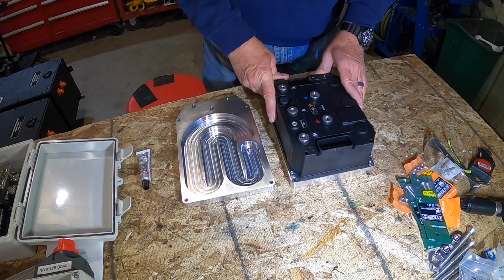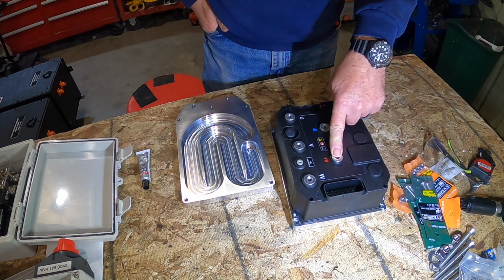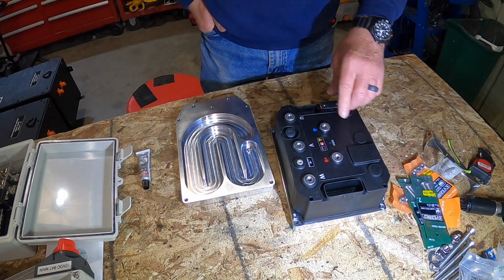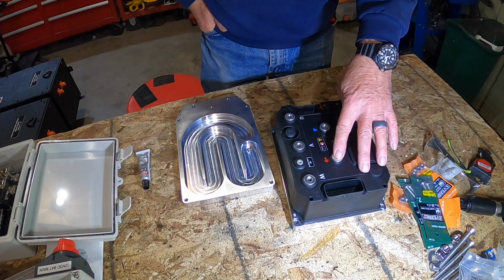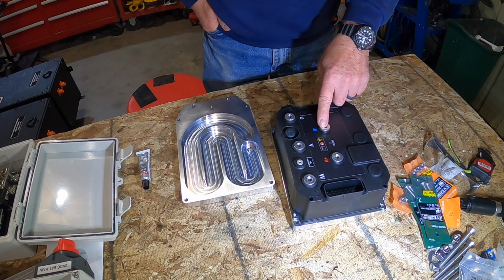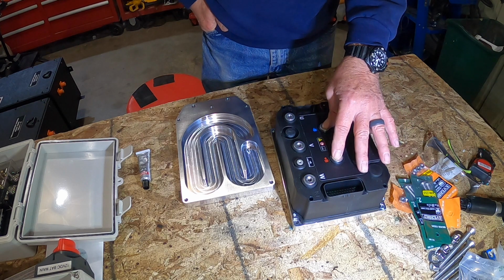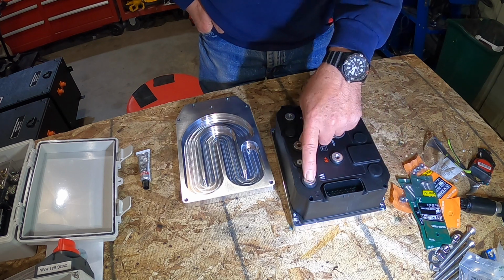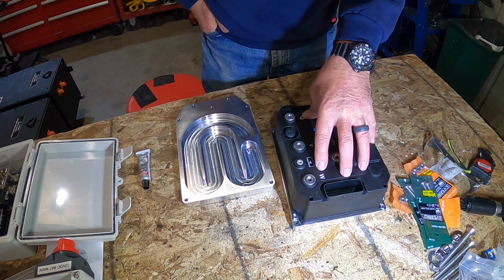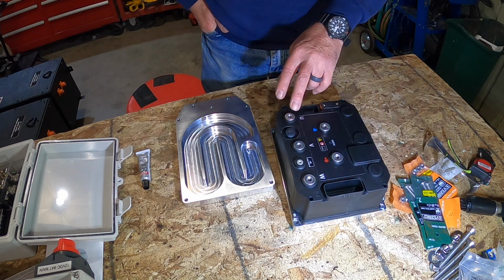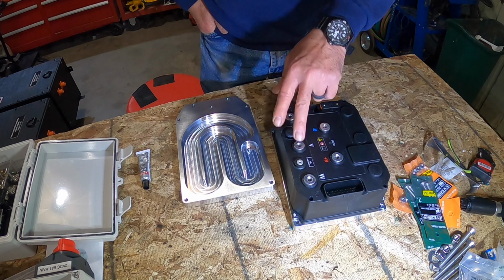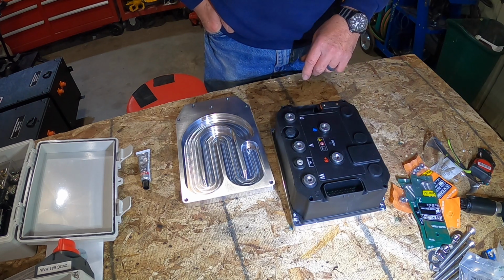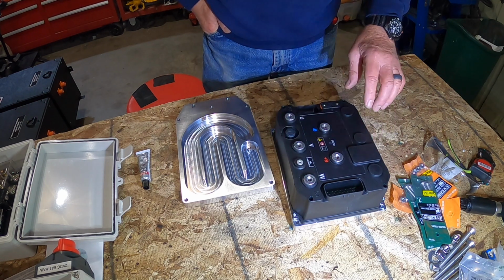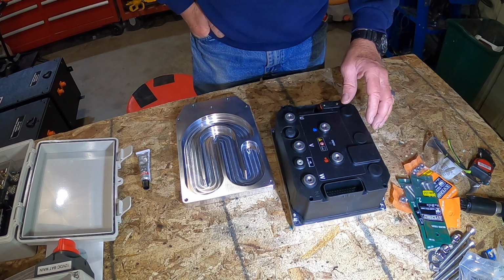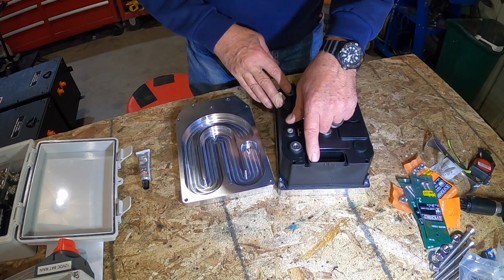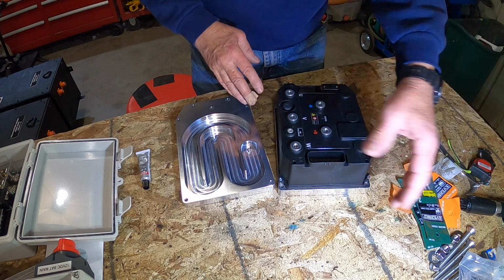Alright, so this is the motor controller. Then I have my positive coming in from the contactor switch in the control box, connected to the battery positive, and then the negative coming in. This is DC, direct current. And then it's going to convert - this is basically an inverter and a motor controller all in one unit - and it's going to convert to 3-phase AC out. So it's basically where Edison meets Tesla here. And then here is my big pin connector for all the control wires.